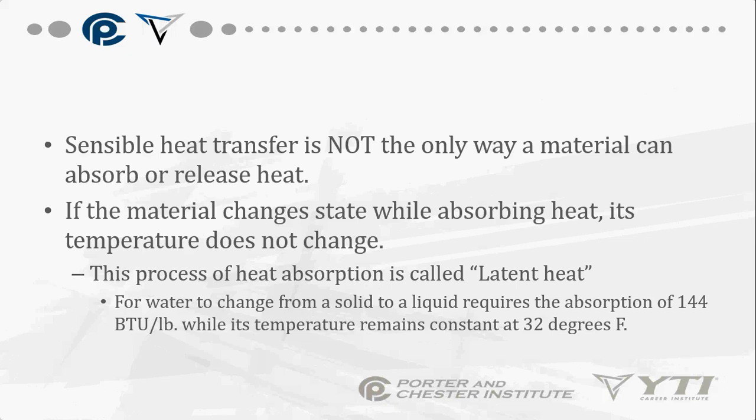Okay, so an example here that they're giving is for water. We're going to have water in a hydronic system no matter what. Okay, so water, to change from a solid to a liquid, requires the absorption of approximately 144 BTUs per pound of water, while its temperature remains constant at 32 degrees.